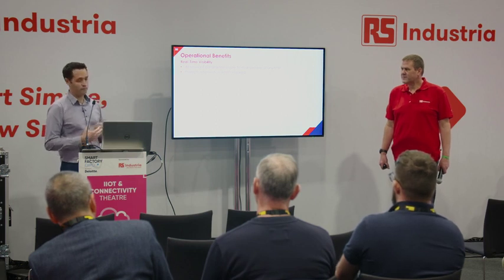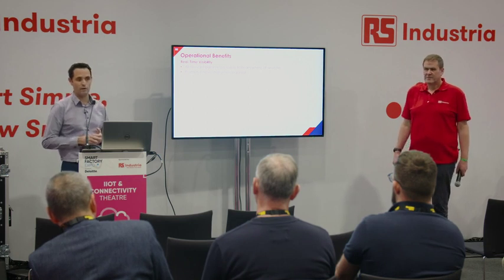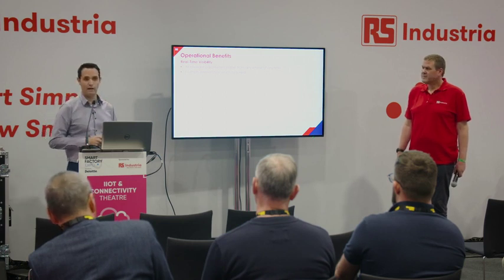So for us, we know that if our pH has gone high, because our acid is dosed in via an IBC, for example, we don't have monitoring on it, but we know when the pH goes high, we know that the acid tank has run out and the plant needs to be replenished.